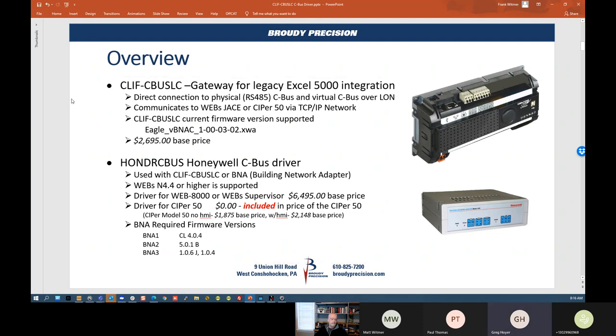A question came up: if you have a CIPer 50, do you still need a gateway — a CLIF gateway? And can you not bring the CBUS directly into one of the 485 ports on the CIPer 50? No — you need the CLIF device. You have to have that either way. The only way to bring in a 485 bus is either the CLIF or with the BNA. The 485 ports on a JACE and on a CIPer 50 will not work for this purpose.